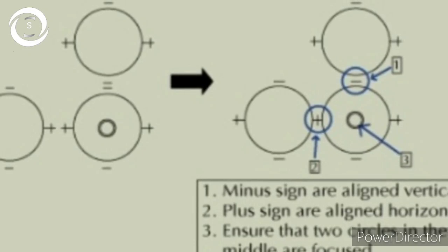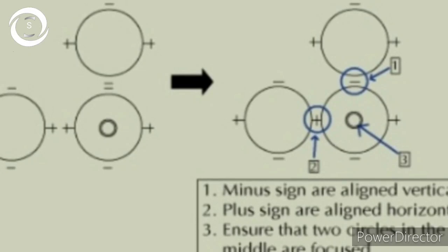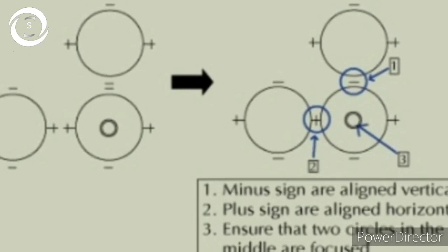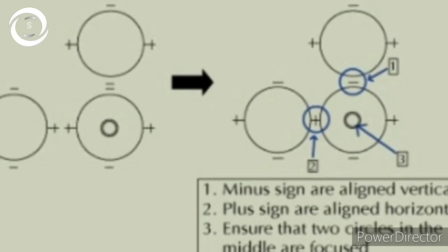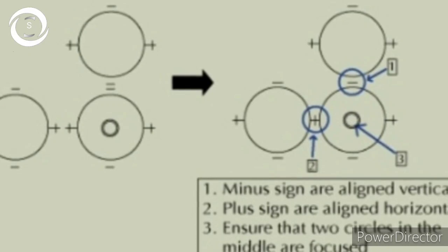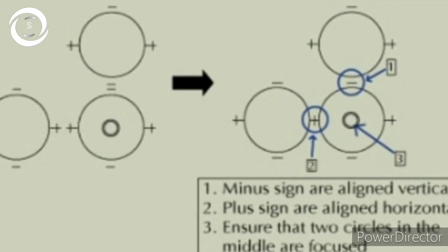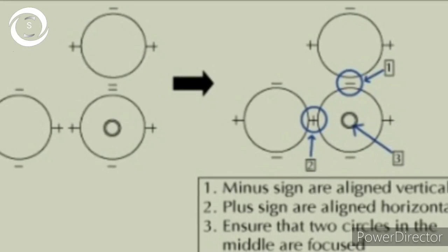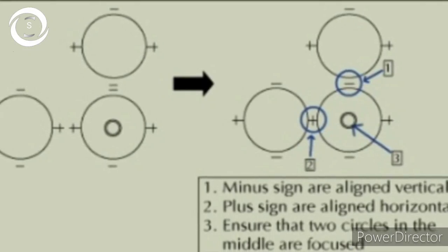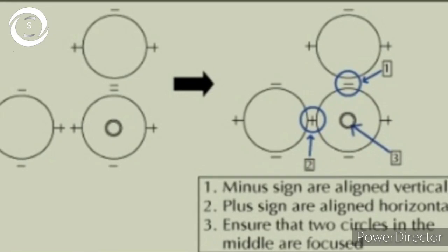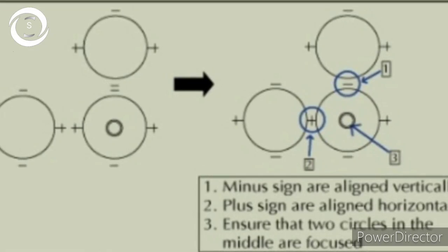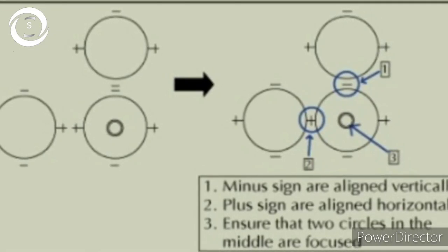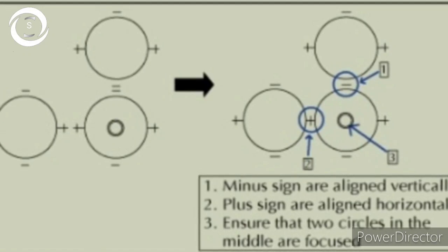You should align the minus of the central image with the minus of the superior image. The plus sign is aligned horizontally with the plus sign of the central image and the plus sign of the horizontal mire. Ensure the two circles in the middle are focused properly as well, so you will get the correct reading of both meridians.